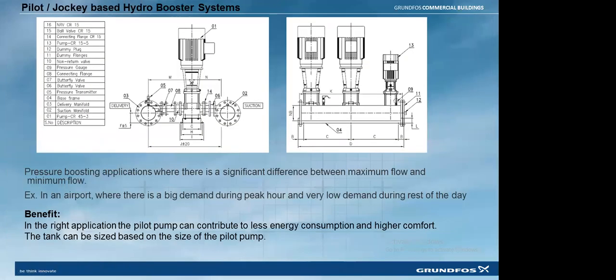Another important new updation in hydropneumatic systems is the pilot pump arrangement. Why do we need this pilot pump arrangement? Of course, we discussed whether we should have a single pump, 2 pump, or 3 pump arrangement. When designing a system for a parallel condition, it is decided based on your load side. Whether you have a very variable load, in a hotel, hospital, airport project, or various kinds of industry, it depends upon your consumption side. We need to decide how many pumps are going to be in parallel.